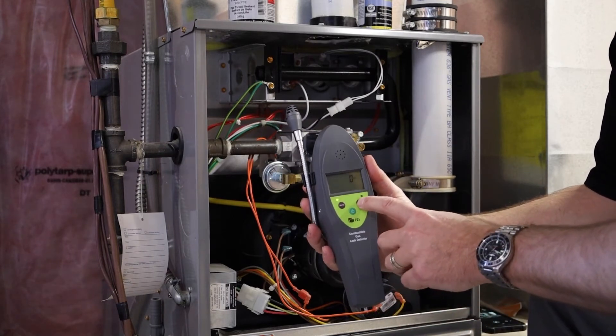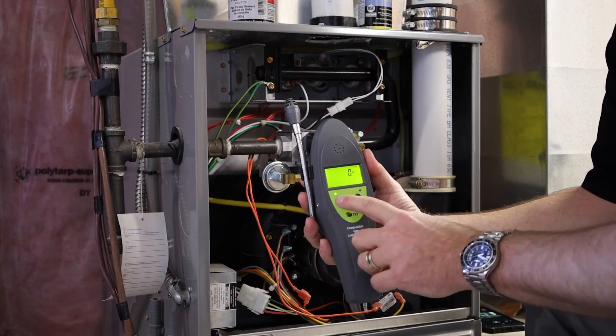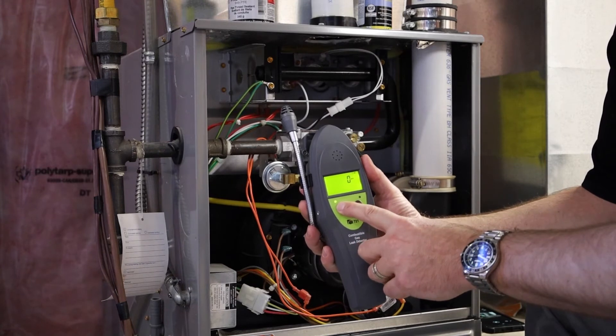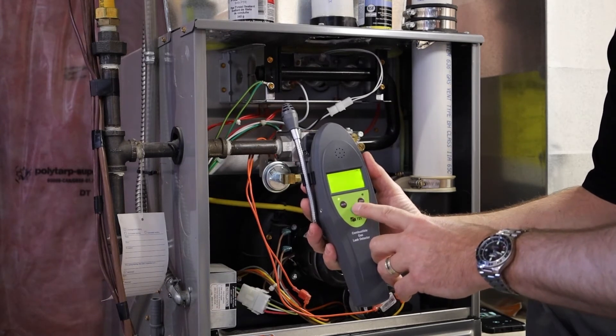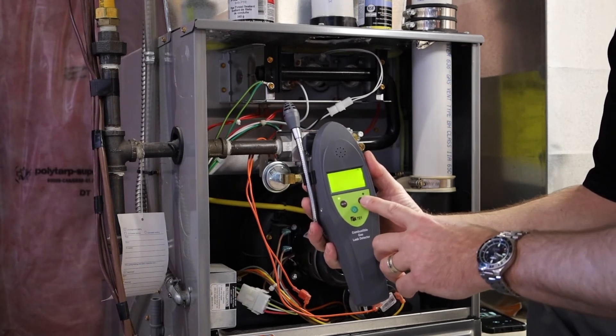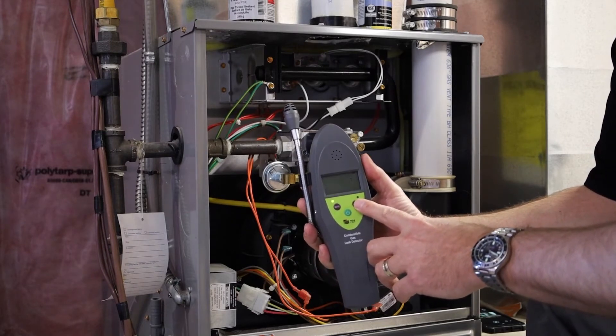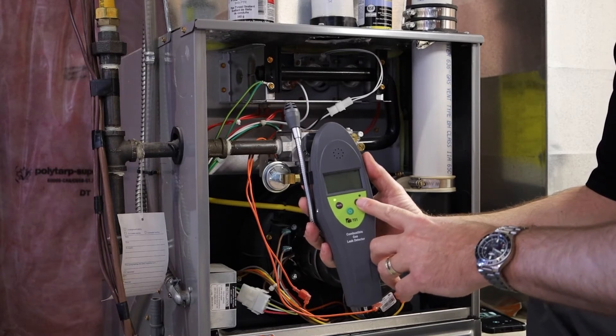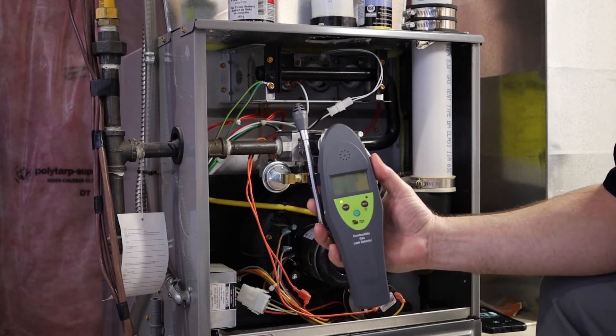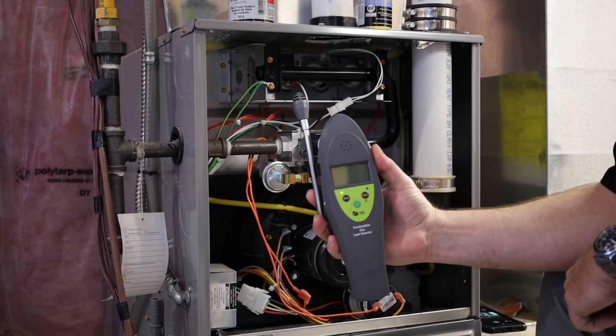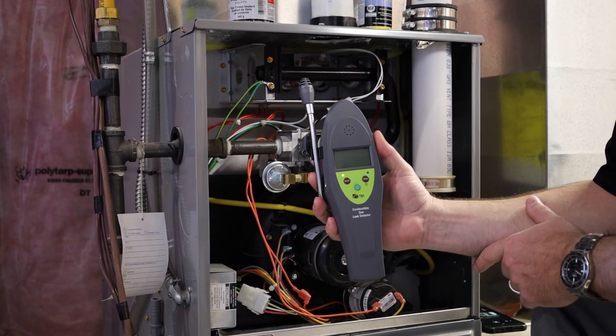Here we have a backlit display. Right now I have it reading in parts per million. But with the push of a couple buttons here, you can actually get it into LEL, so percent LEL, or stepped. These steps would be one, two, three, four, five, and they're going to represent different levels of leak. One would be 500, then up to 1,000, 3,000, 5,000, up to 10,000 parts per million.